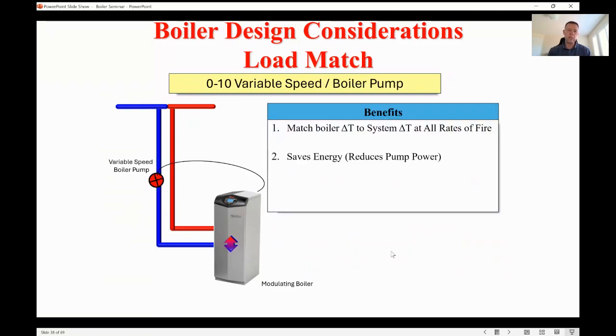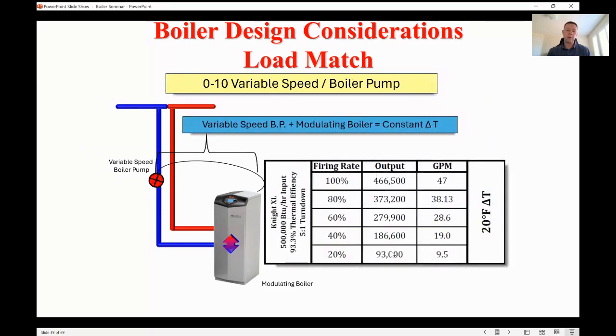But with a VFD pump, there'll be an output from the boiler to that pump, and that'll basically drive it, right? So as that boiler ramps down, the delta T stays constant, so it ramps the flow down. As that flow ramps down, it's always going to keep it at that 20-degree temperature rise, and you're going to achieve a little bit of electrical savings here.